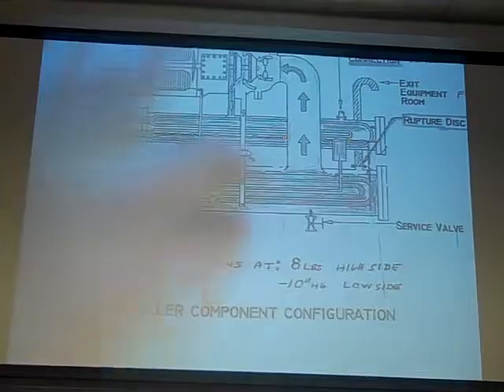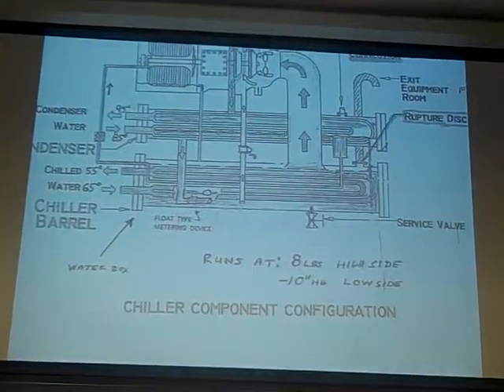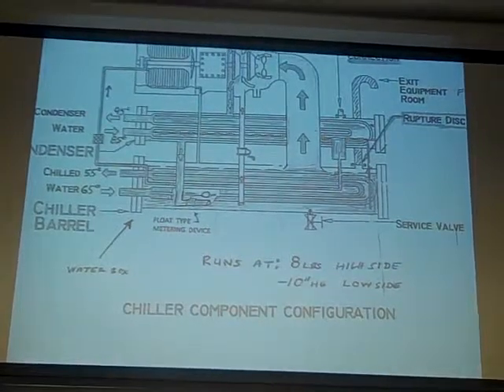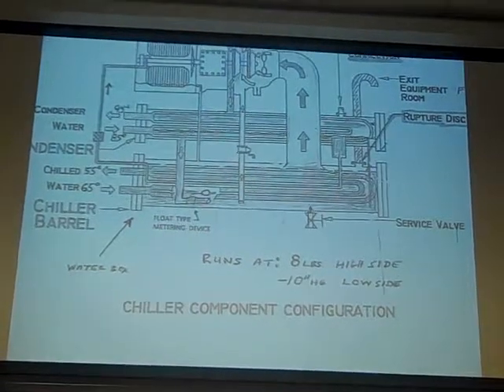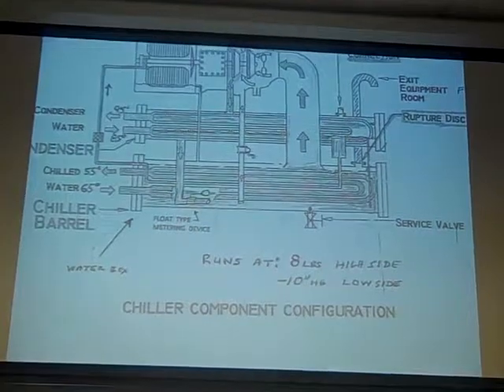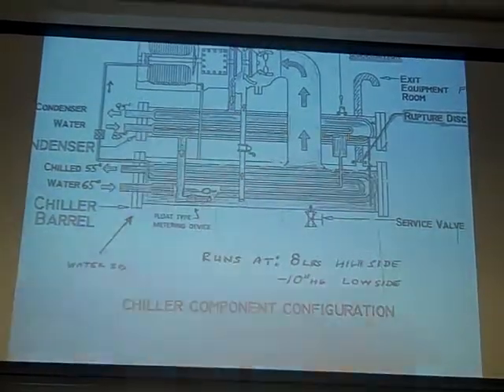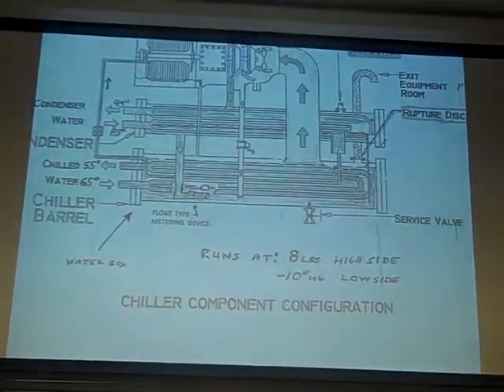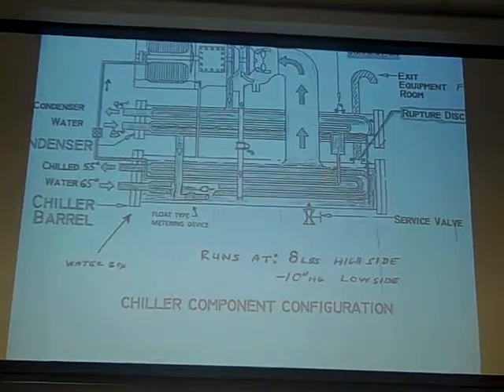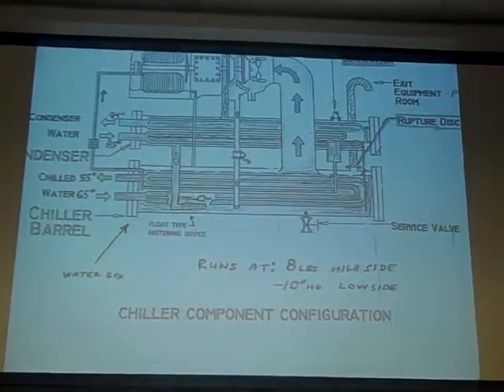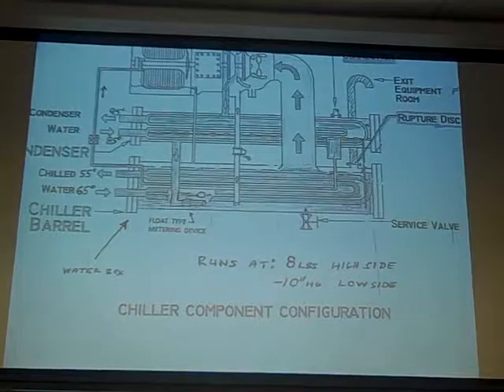So this part, normally, this part here, you won't be able to feel that tube. It's usually covered with about 3 inches of heavy black insulation. It's 55 degrees, it's nice and cold. The top one is usually open, just metal. Usually runs around 95 degrees, 95 to 100 degrees. So there, feel, it's nice and warm. That's just the condenser side of it.